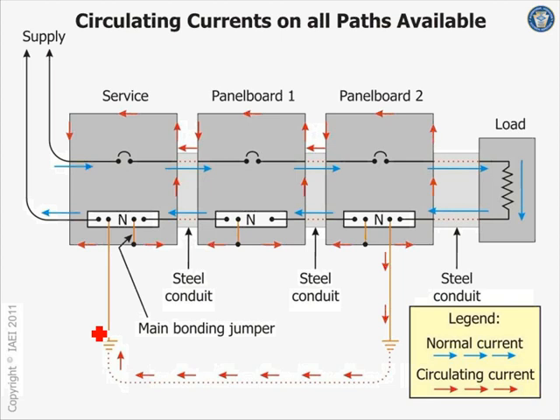This power system above your head is in normal operating condition, right? There's no short, no ground fault that we know of. So the current is going right through wherever. That's your so-called circulating current, and that's what you eliminate when you bond the neutral only once at the service. Any comments, guys? Any questions?